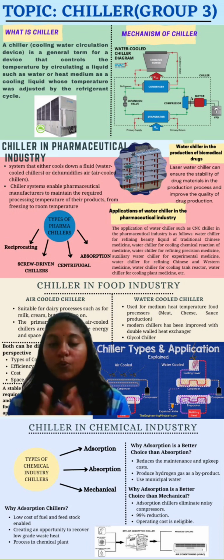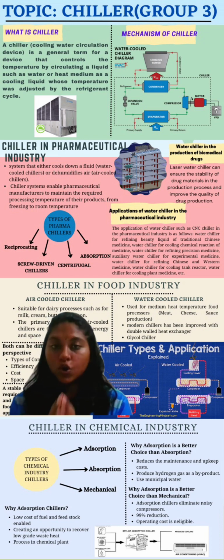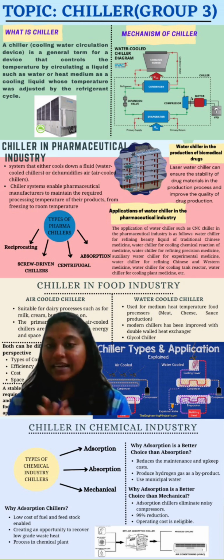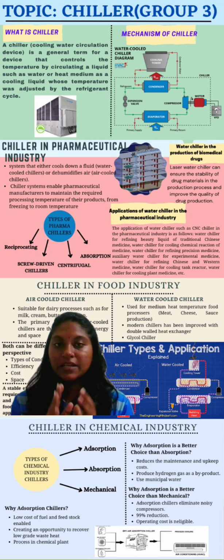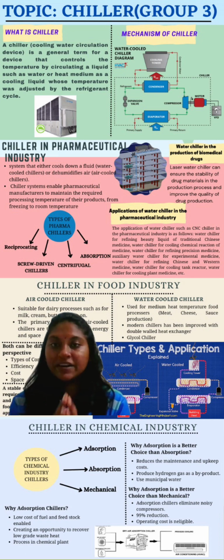These chillers come with a water or air condenser, reciprocating compressor motor assembly, an expansion device, control panel and wiring, a compressor motor starter, interconnecting refrigerant piping, and oil and refrigerant charge. Second, screw-driven chillers. Screw-driven chillers with screw compressors usually have capacities of under 300 tons. They are called positive displacement devices because they compress refrigerant by reducing the refrigerant chamber's size.